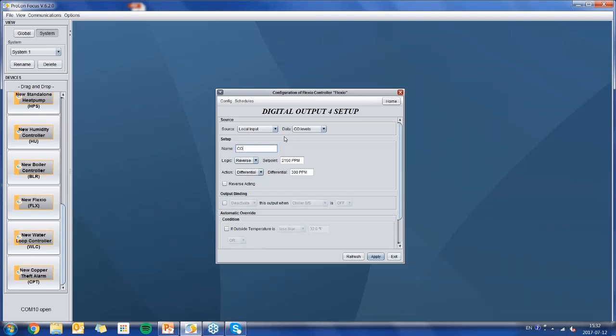Obviously we would want it to be direct acting, so as the levels go up, we want to initiate it. Maybe I'll put 20 ppm with a differential of, let's say, 4 or something like that. So once I go here, I'll know that my carbon monoxide evacuation sequence will start at 22 ppm, and we will deactivate it once it goes down to 18 ppm. There we go, okie doke.